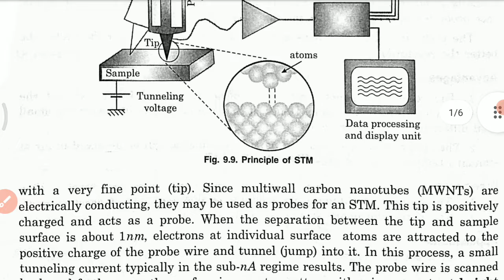The probe wire is scanned back and forth across the surface in a raster pattern, either in a constant height mode or in a constant current mode. So accordingly there are two modes of operation. And one more thing is that the STM can only scan conducting surfaces.